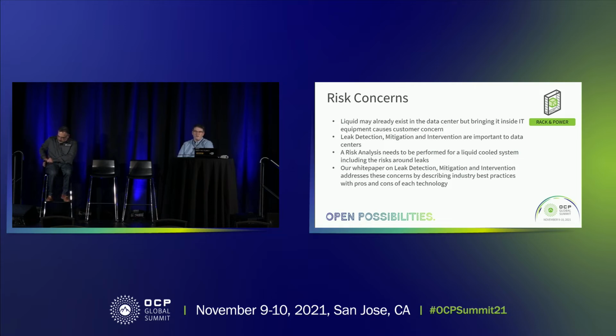Rear doors have been out in the industry for a while. That got liquid very close to the IT equipment, but cold plates are another form of liquid cooling, whether water-based or a refrigerant. It's actually going within the server, and there are challenges with that. There are risks associated with it, but also a lot of rewards.